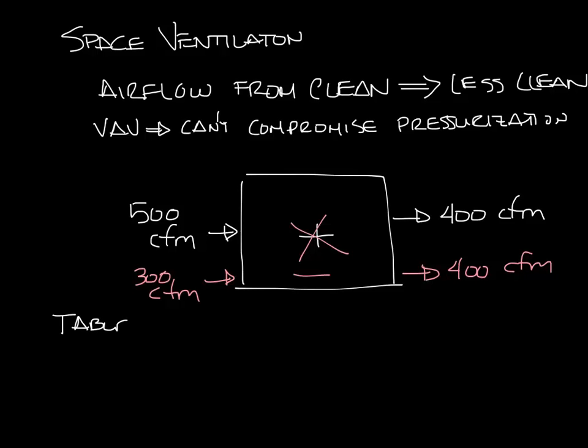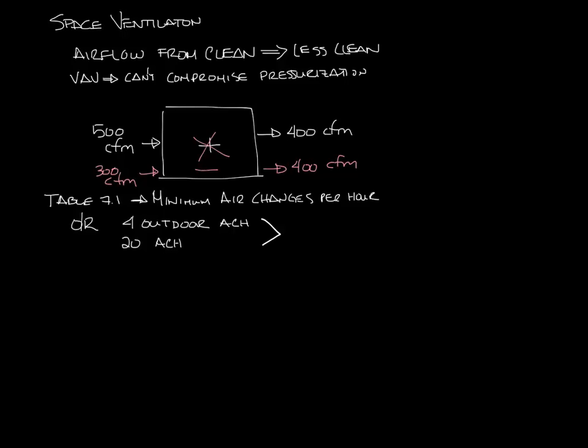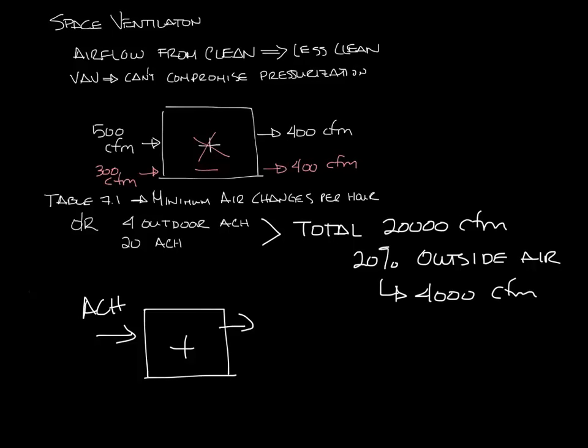Table 7.1 shows the minimum air changes per hour required for a given space based on the type of space it is. For instance, in an operating room you need 4 outdoor air changes per hour and 20 total air changes per hour. This means you have to bring in the equivalent of 4 outdoor air changes as part of those 20 air changes. So if you have 20 air changes equaling 20,000 CFM, you'd set your outside air damper at about 20% to get 4,000 CFM of outdoor air. Also, if a space is supposed to be positively pressurized, the air changes are measured by what's supplied to the space, and if the space is negatively pressurized, it's measured by what is exhausted from the space.